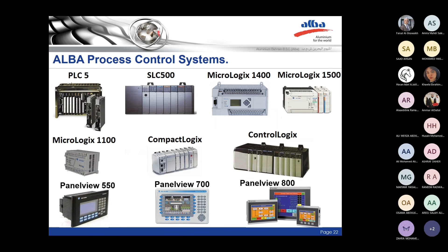The PanelView, or sometimes we name it HMI, Human Machine Interface. So the software will be there, where a graphical view and all the numerical data from the PLC will be shown. Some of the PanelViews will be only for monitoring, so he will only be able to read the data. In some of them, he will be able to control, to close some valve, to start one motor, to stop a motor, and so on. All these types of PanelView are widely used in ALBA.